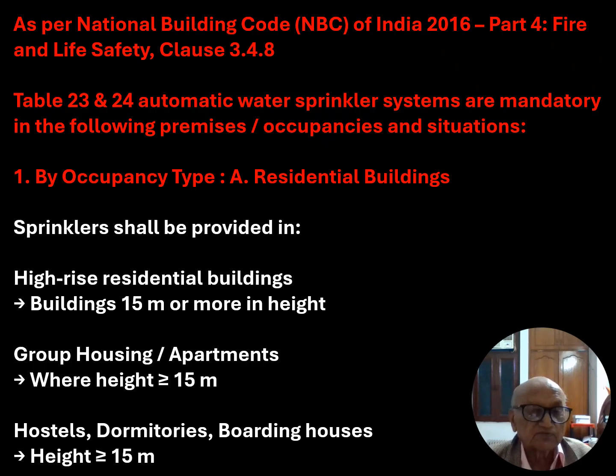Sprinklers shall be provided in high-rise residential buildings 15 meters or more in height as per the National Building Code. Any building more than 15 meters is known as a high-rise building, whereas in other codes worldwide it is 35 meters. But in India they have taken it as more than 15 meters. Now let us talk about where sprinklers are to be provided: in group housing apartments where height is more than 15 meters, and hostels, dormitories and boarding houses having height more than 15 meters.